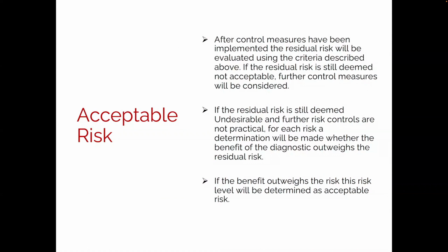If you're in the middle zone, then you're really talking about, can you reduce the risk even further? Is it practical to do a redesign? But you're in this middle zone where you can make a judgment call in terms of, does the benefit of the device outweigh some of that residual risk? And if the benefit outweighs the risk, then you can determine that it's actually acceptable.